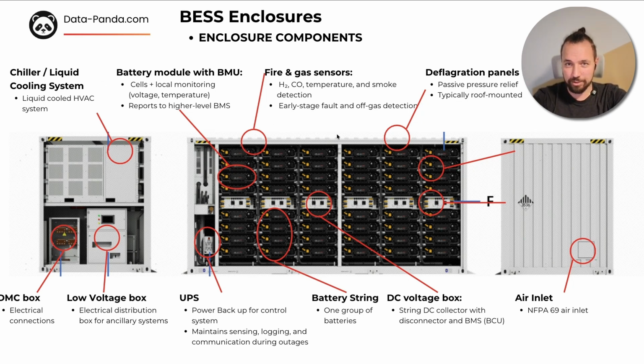On top of some of the enclosures, we can also have a deflagration panel. It's NFPA 68 design, not 69 but 68. And this is a passive safety device. They are not doing any fire suppression. The function is that if inside the container pressure rapidly builds up due to gas ignitions, these panels will open in a controlled way to release this pressure. And you can look at it as, for example, if there is an explosion inside the container, because we have hydrogen generation, it will release this pressure on top instead of front.